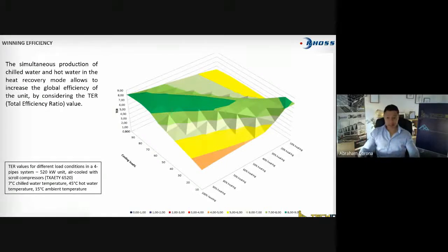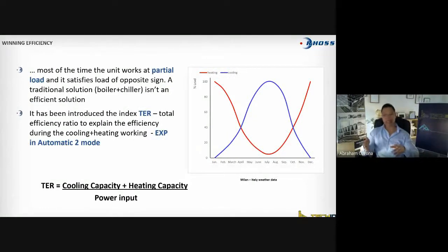I do another parenthesis, that is my experience in the market, and this is more targeted even to consultants. It is about efficiency, all right? We need to introduce a new term, what we call total efficiency ratio. The total efficiency ratio is no more than the cooling capacity and heating capacity divided by the power required to get those capacities, all right?